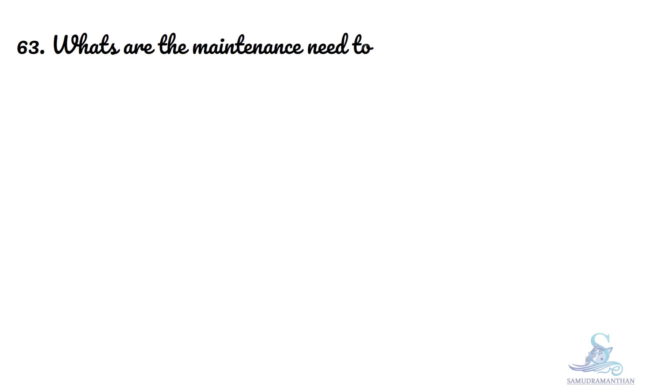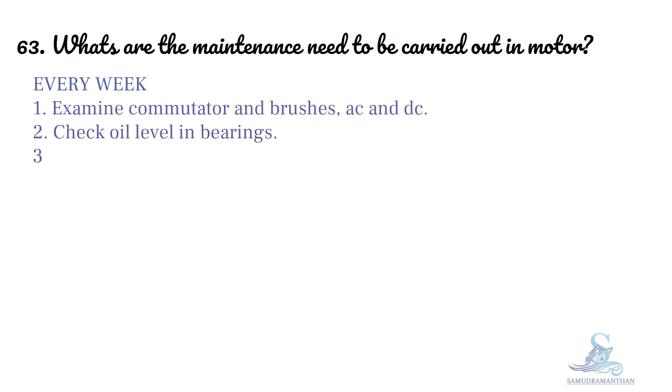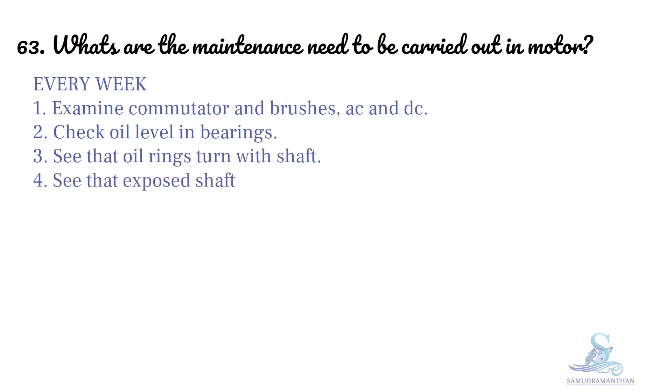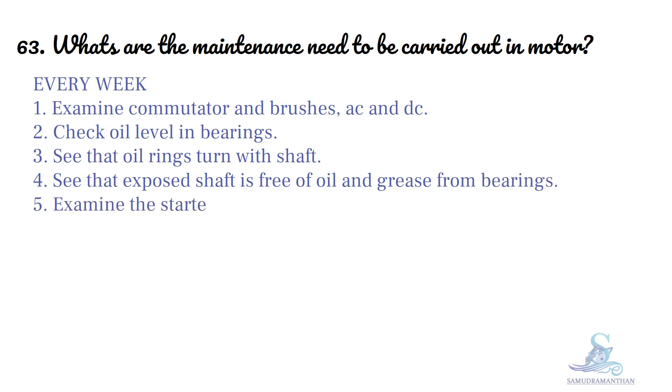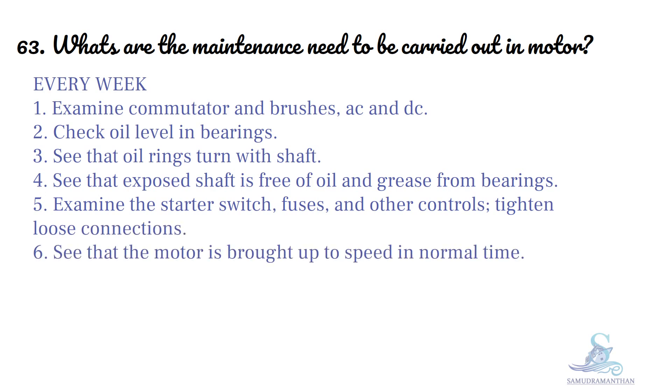What are the maintenance needs to be carried out in a motor? Every week: examine commutator and brushes (AC and DC), check oil levels in bearing, see that oil rings turn with shaft, see that exposed shaft is free of oil and grease from bearings, examine the starter switch, fuses, and other controls, tighten loose connections, and see that the motor is brought up to speed in normal time.